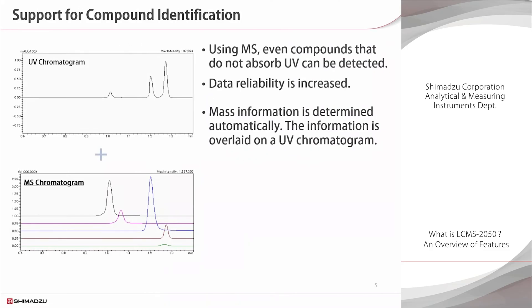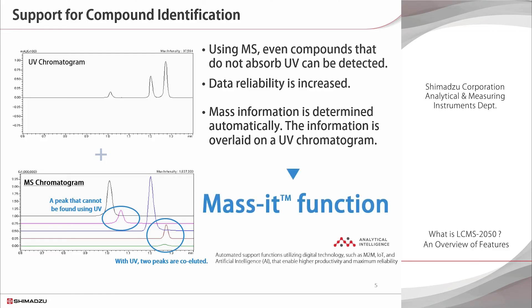The primary advantage of mass spectrometry is the wealth of information it provides. Even compounds that do not absorb UV can be detected, and co-eluted compounds are not overlooked. Further, using the proprietary Mass-it function built into the LC-MS 2050, the mass information can be checked by overlaying it on the UV chromatogram data. The LC-MS 2050 is a powerful tool for analyzing not just known compounds but also unknown samples.